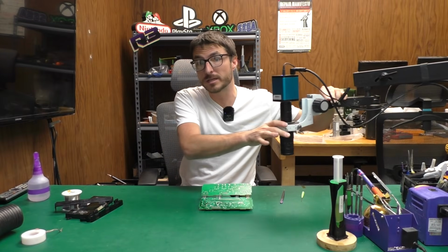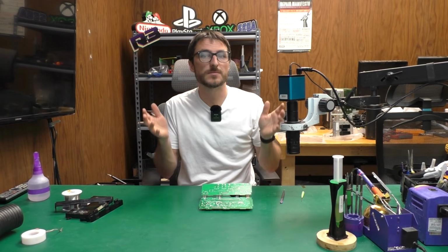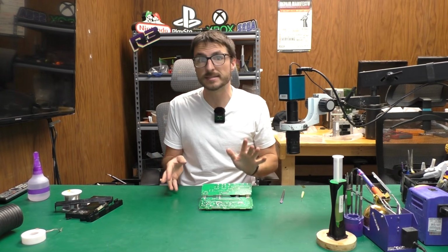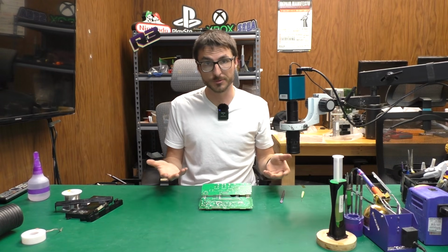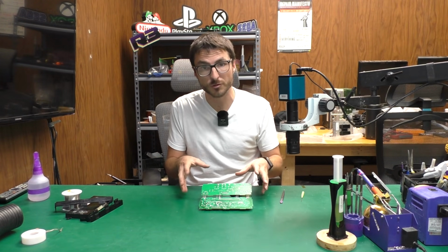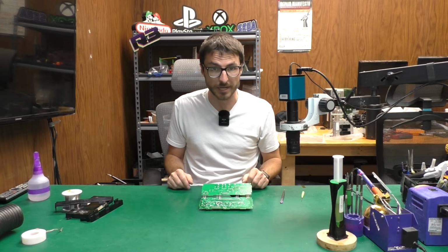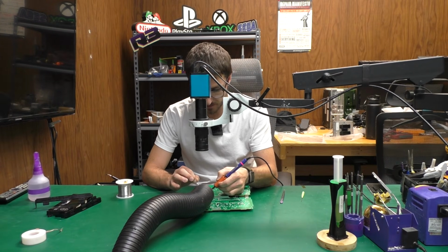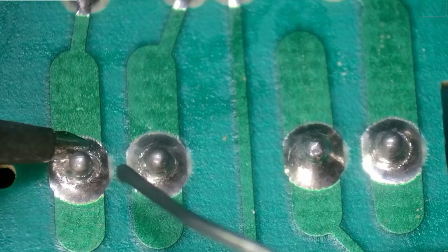Now, the reason we are looking at those joints specifically is because that connector is where we connect our thermal sensor. When the thermal sensor is not detected by the controller board, it will throw an F3 error code. In order for us to fix this, we will have to resolder the joints.